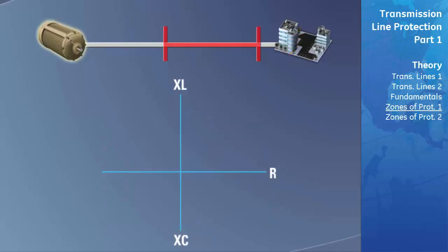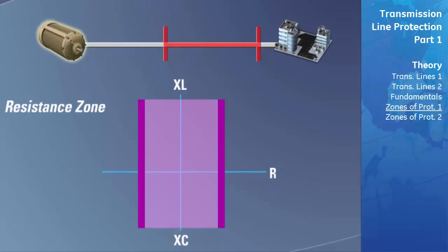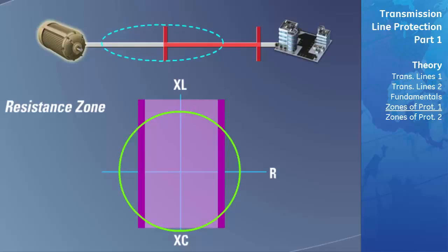The next zone of protection is a resistance zone, used to detect when the impedance of the fault has a very high inductive component. If the fault does have a high inductive impedance, this indicates there is very little or no resistive load at the end of the transmission line and the fault is likely located on the transmission line. This type of zone is usually never used to trip a transmission line on its own but is normally used to supervise another distance zone. For example, the resistive zone can verify that a fault is actually on the transmission line because the impedance is mostly inductive, giving the impedance zone permission to trip.